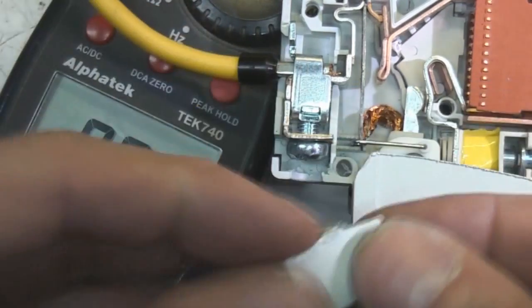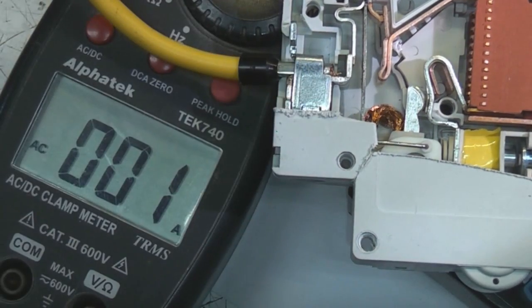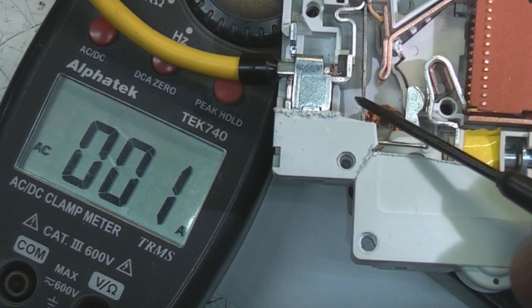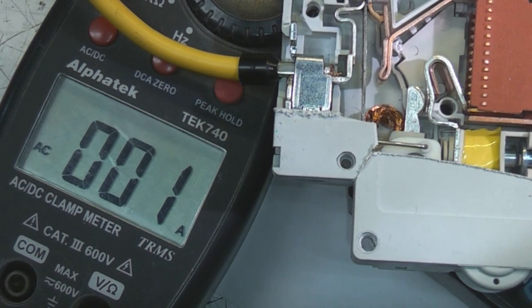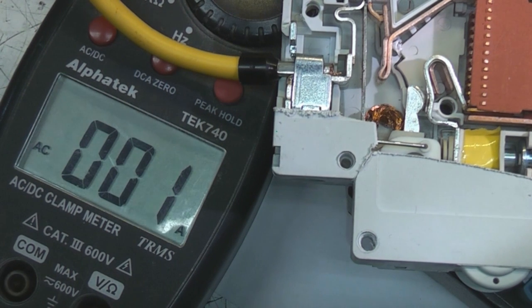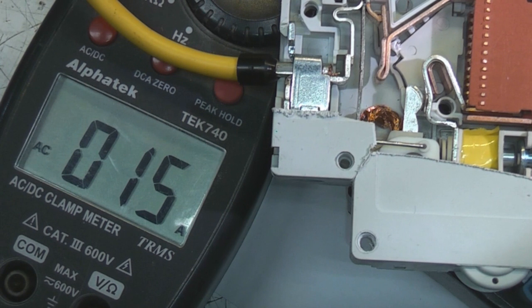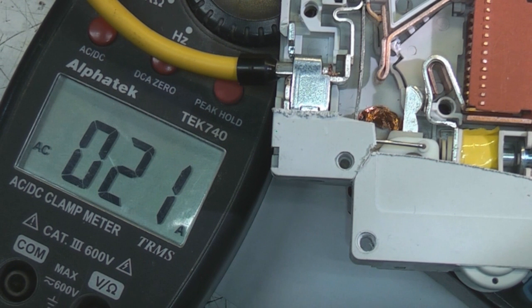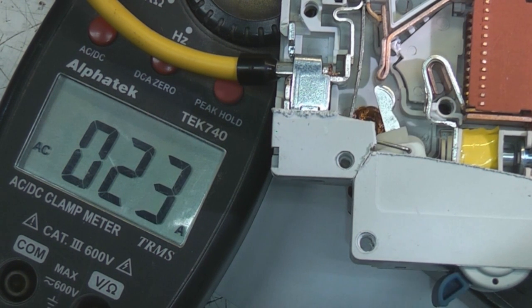Right, so if we look at the thermal aspect of it, I've got to put this cover on because these guides hold this pin in place. But what we see is as we increase the current, you'll see this strip bending to the left until it pulls this lever and opens the breaker. So if we go up to sort of 10 amps, that's its normal running current, so it should sit there pretty much all day long. As we increase it, we should start seeing this strip bending over to the left. It's 20 amps, and there we go, tripped.